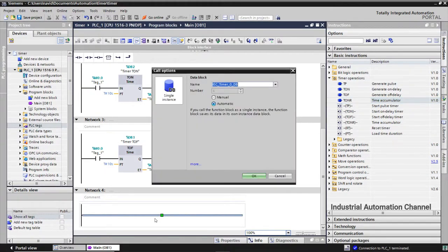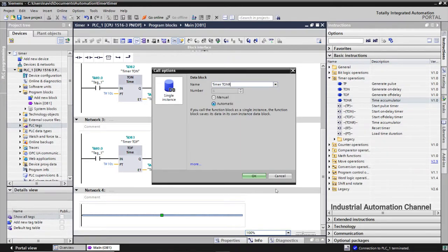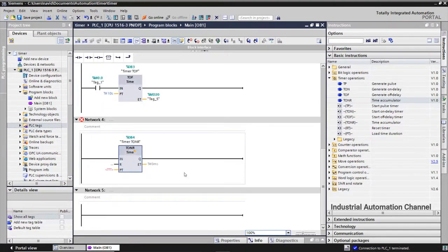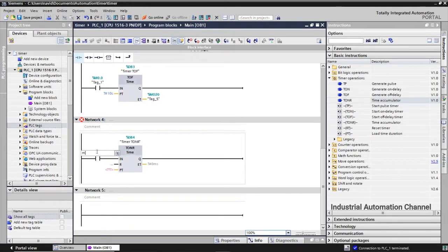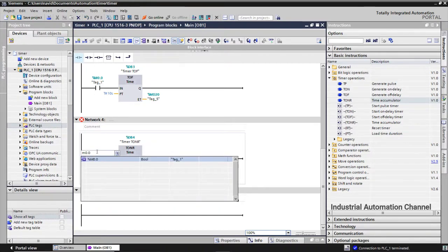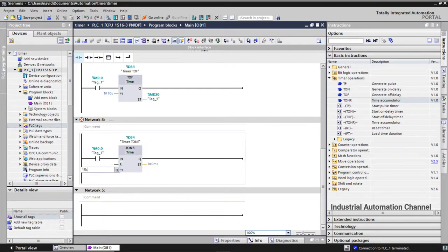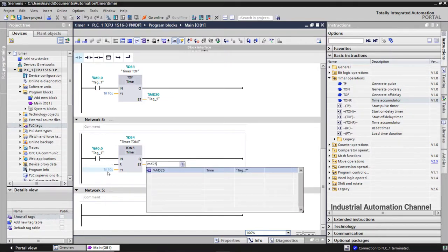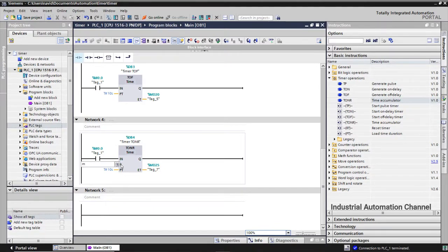Like other timers, we have a data block to save the timer's data and we need to define a name for it. We have input preset time, elapsed time, and output, the same as the inputs and outputs in other timers. But we have here an extra reset input. We can reset the time with this input.